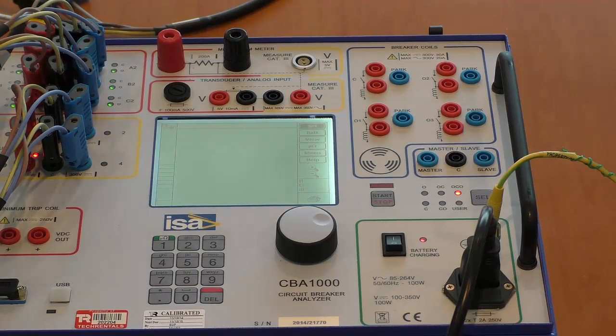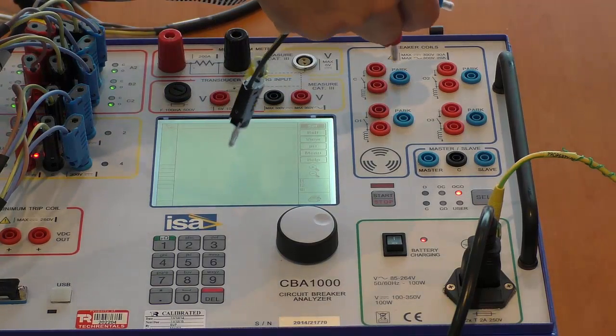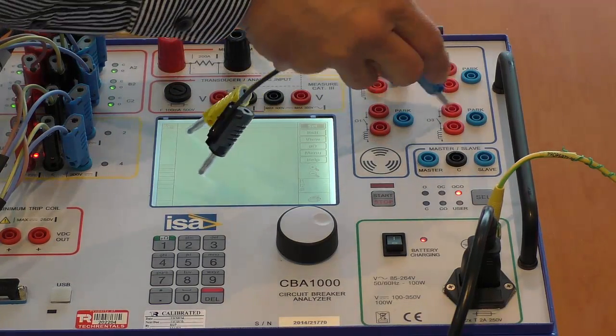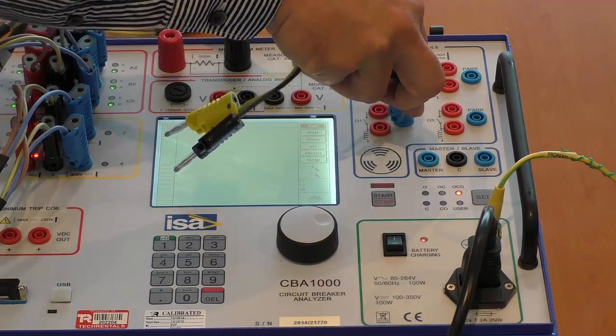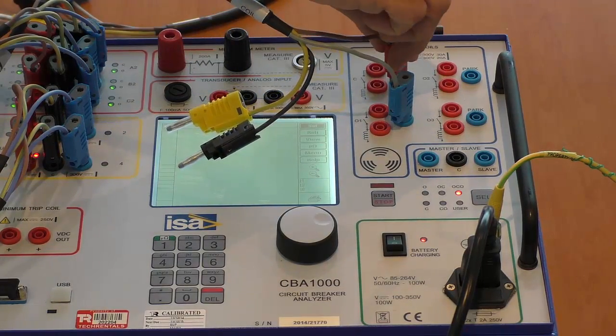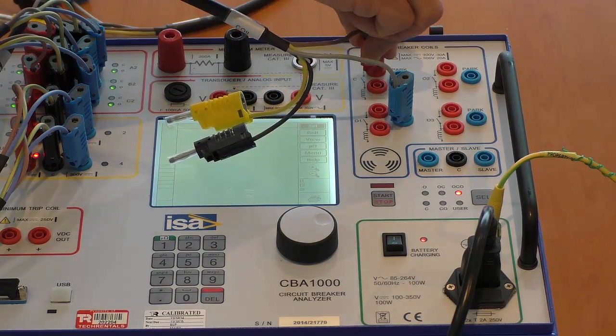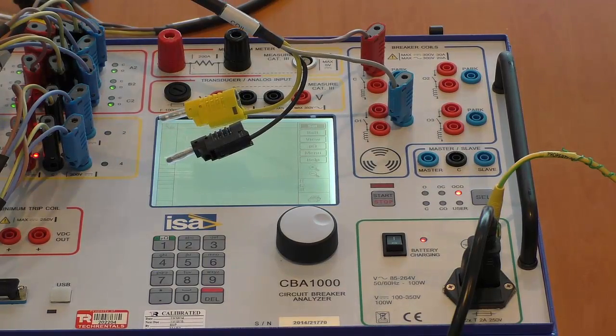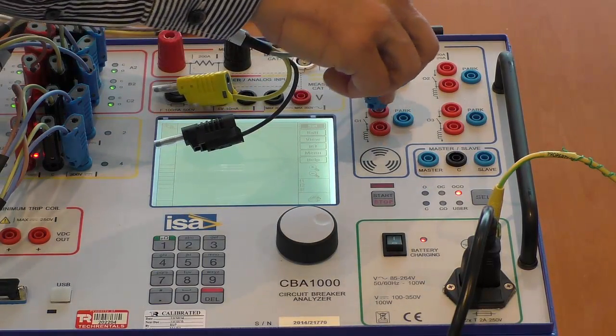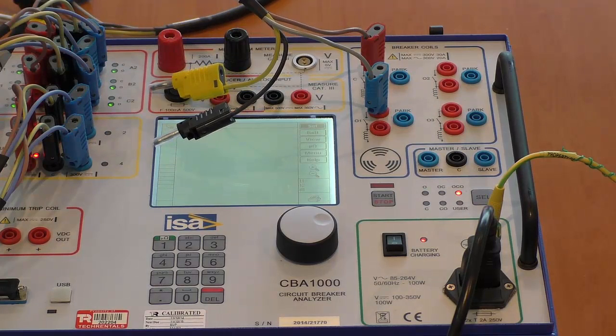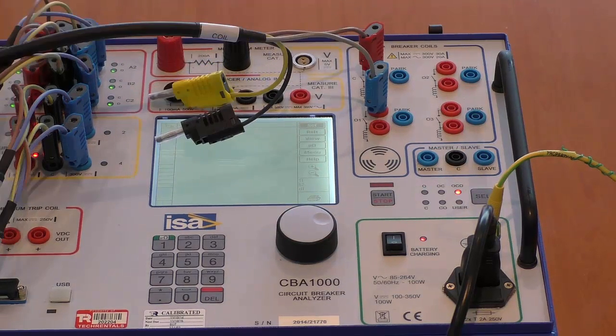In order to control the circuit breaker, to open and close the circuit breaker, DC from the substation has to be provided to the actual circuit breaker timer. Initially the DC is provided into the park terminal, which is a blanked off terminal. This terminal is then later moved to the actual top of the close circuit and the top of the open circuit once you're ready to initiate a trip or a close. This is done for safety purposes.